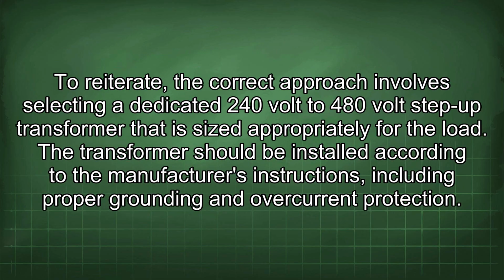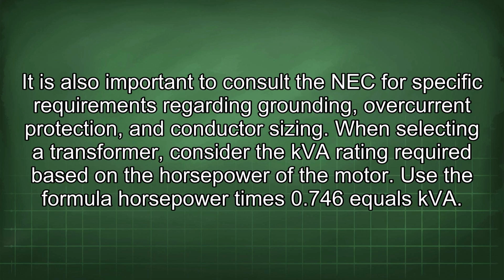To reiterate, the correct approach involves selecting a dedicated 240 volt to 480 volt step-up transformer that is sized appropriately for the load. The transformer should be installed according to the manufacturer's instructions, including proper grounding and overcurrent protection. It is also important to consult the NEC for specific requirements regarding grounding, overcurrent protection, and conductor sizing. When selecting a transformer, consider the kVA rating required based on the horsepower of the motor.